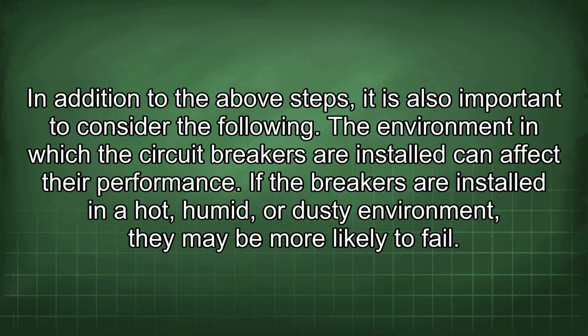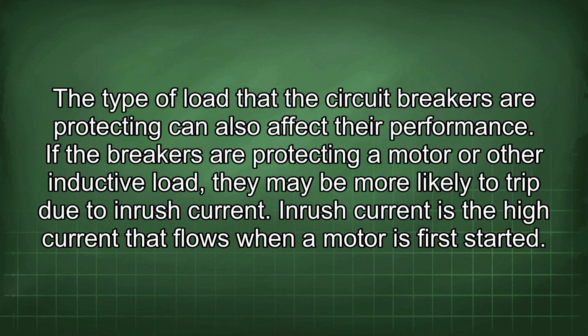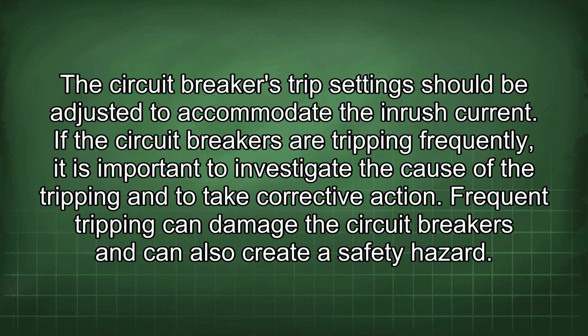In addition to the above steps, it is also important to consider the following. The environment in which the circuit breakers are installed can affect their performance. If the breakers are installed in a hot, humid, or dusty environment, they may be more likely to fail. The type of load that the circuit breakers are protecting can also affect their performance. If the breakers are protecting a motor or other inductive load, they may be more likely to trip due to inrush current. Inrush current is the high current that flows when a motor is first started. The circuit breaker's trip setting should be adjusted to accommodate the inrush current.